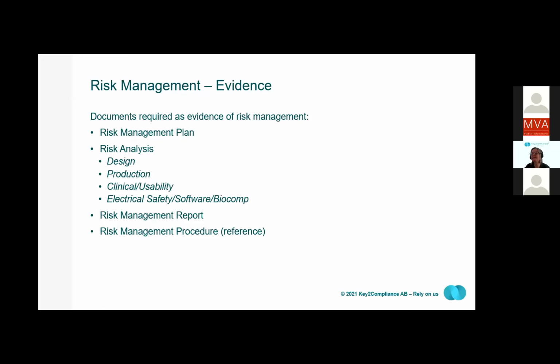I would say the risk management section is not that different in MDR from the MDD requirements, since it would probably still be 14971. That is the state-of-the-art method, even if the standard is not yet harmonized with MDR. MDR also talks a bit more about being an iterative process throughout the entire life cycle of the device with regular systematic updates, and also points out that the risk management plan needs to be established for each device and so on. But these have usually already been implemented if using 14971. The risk management requirements are more clearly defined in MDR compared to MDD, and the risk management is one of the core areas in the documentation, since it relates to so many other documents.